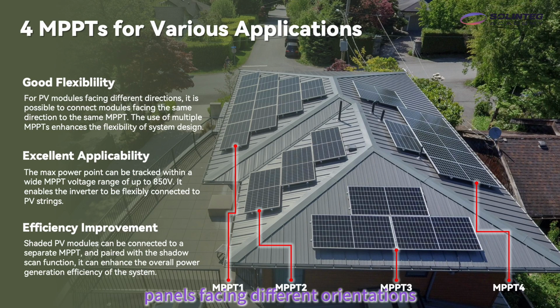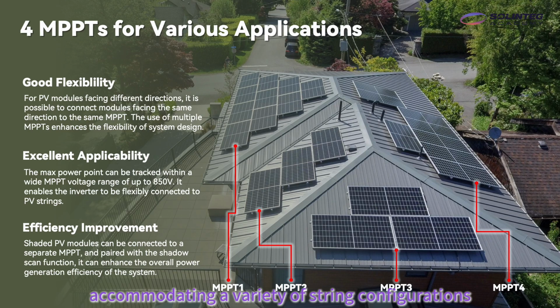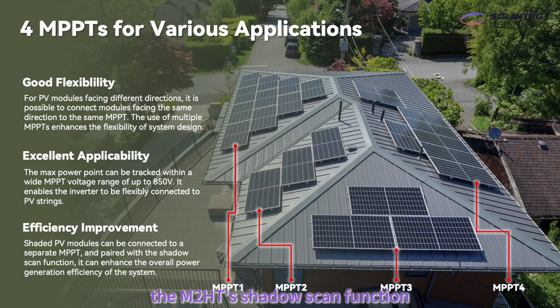Panels facing different orientations can each be connected to their own MPPT, ensuring each string is tracked and optimized independently rather than one underperforming string dragging down the rest. The wide MPPT voltage range of up to 850 volts also adds to this flexibility, accommodating a variety of string configurations across different roof layouts or ground mount designs. And for sites with partial shading, the M2HT's shadow scan function works alongside the independent MPPTs to minimize the impact of shading on overall system output, protecting the end user's energy yield even in less than ideal conditions.